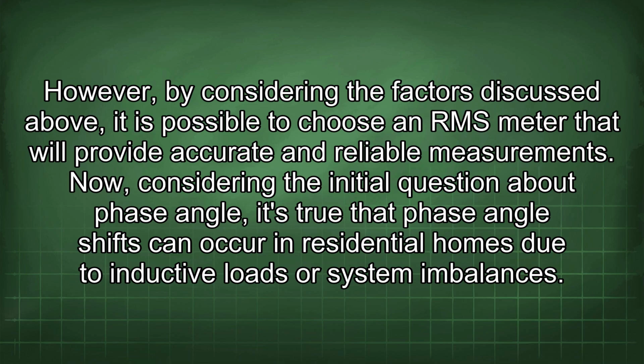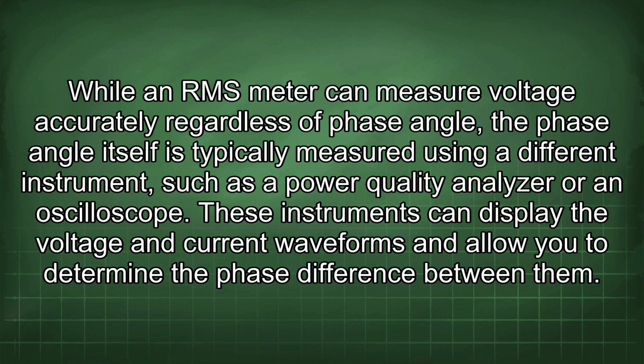Now, considering the initial question about phase angle, it's true that phase angle shifts can occur in residential homes due to inductive loads or system imbalances. While an RMS meter can measure voltage accurately regardless of phase angle, the phase angle itself is typically measured using a different instrument, such as a power quality analyzer or an oscilloscope. These instruments can display the voltage and current waveforms and allow you to determine the phase difference between them.